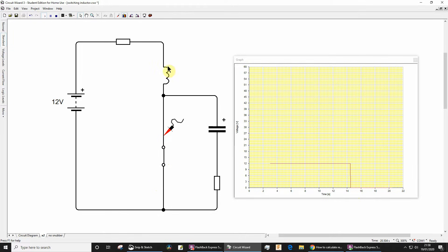This was the thing - we've got the current flowing through the inductor and therefore there's going to be energy in that inductor. When we open the switch, normally what would happen is the transient voltage will rise to keep that current flowing, but we have or will have that transient voltage capped to approximately 50 volts because I've chosen appropriate values for R and C.